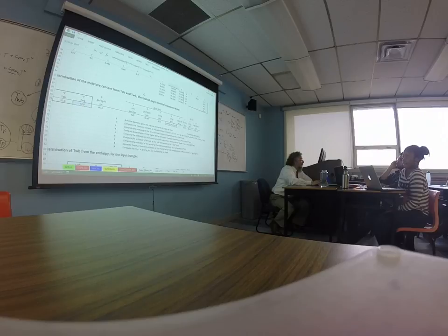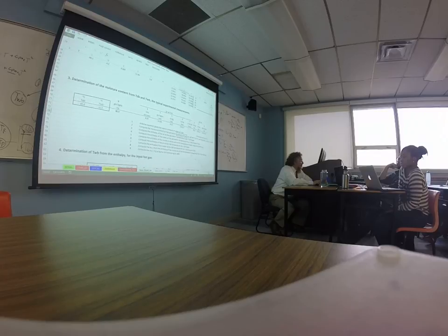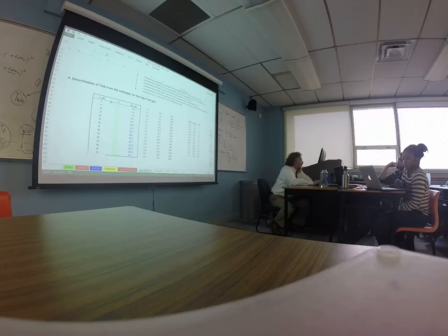You see how the specific heats use the temperatures, squared, linear. This D71 is this here, and then multiplied by temperature. So that's by HW. All the things in the bracket are the specific heat multiplied by temperature. So that's one piece of information you have here, and then you have another example of calculations, but at different wet bulb temperatures. You have different enthalpies, different moisture content, saturation pressure, enthalpy of the air, enthalpy of the water.